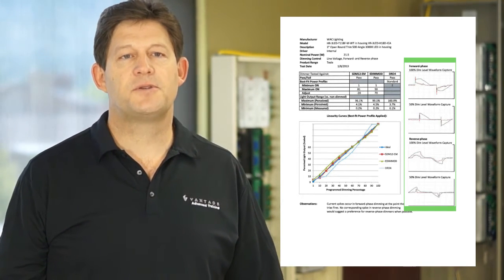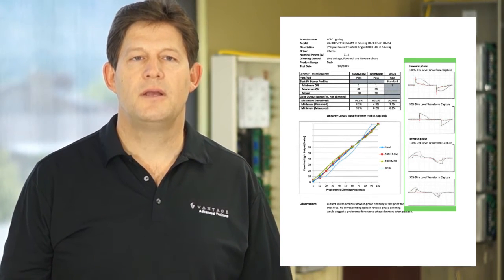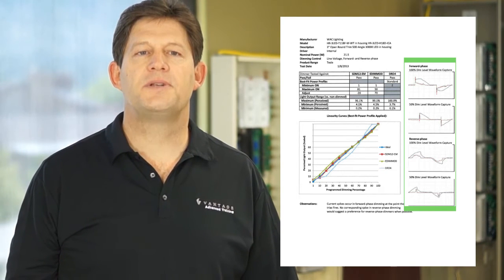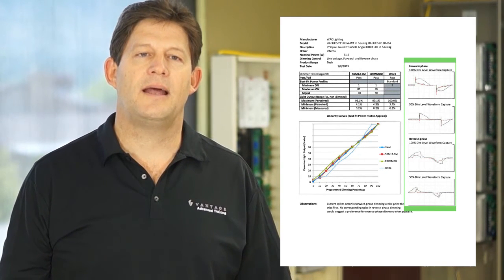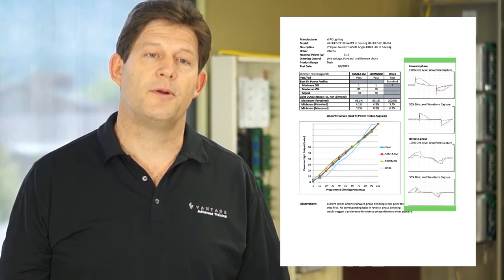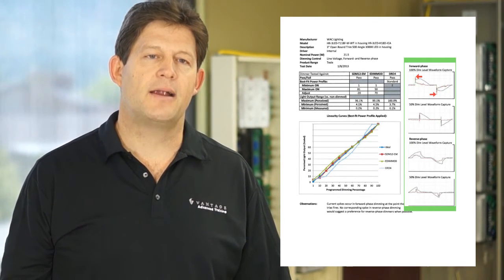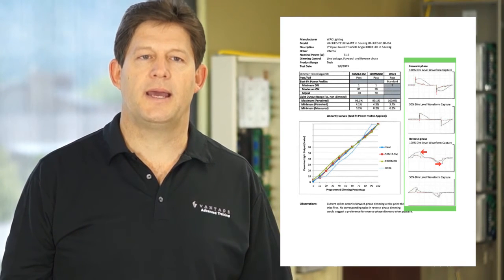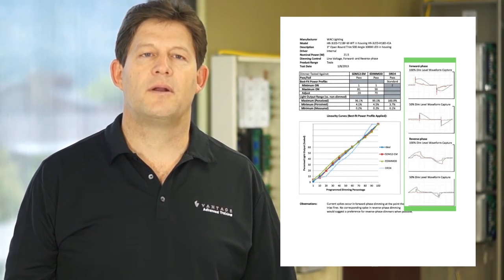Finally, we have the observation section, where flicker, smoothness issues, minimum load issues, and the like are recorded. In this particular report, we point out that on a forward phase dimmer, there is a sharp current spike where the triac fires. And on the reverse phase dimmer, there is no corresponding spike, but a better behaved current waveform.